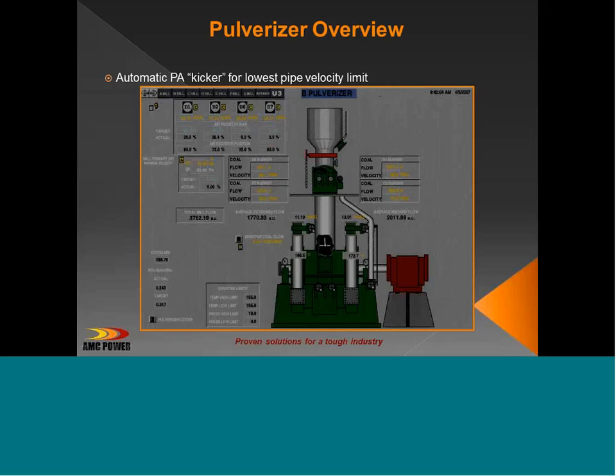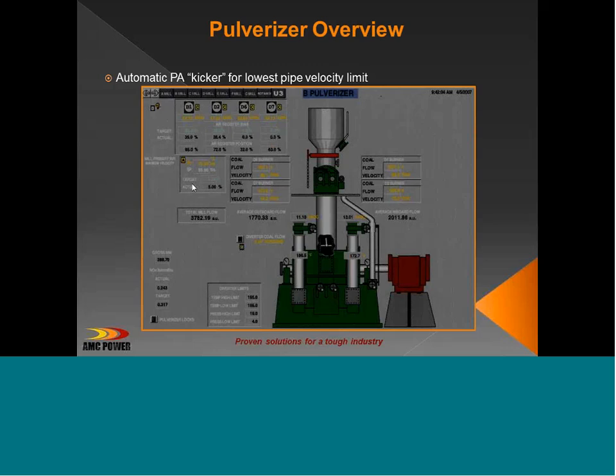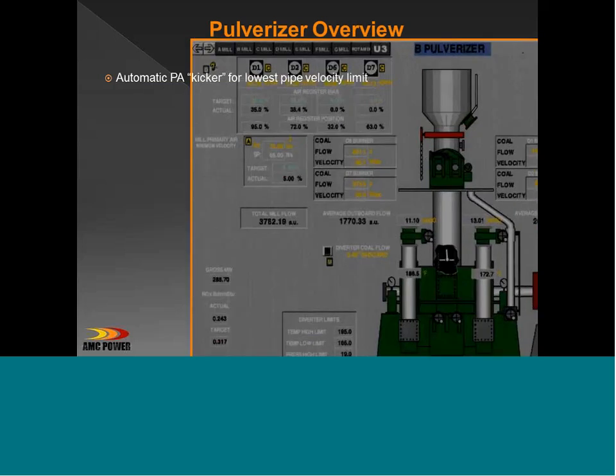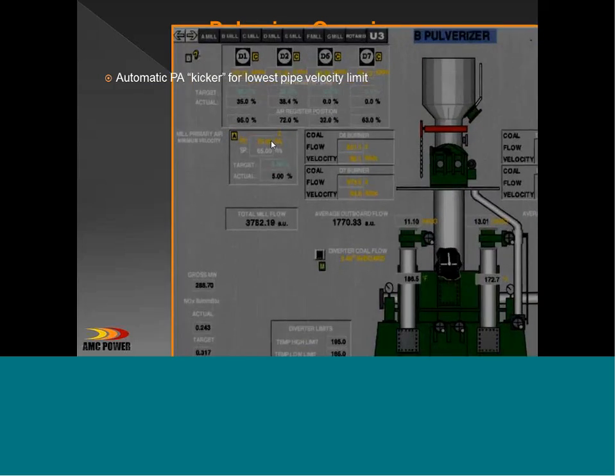But what this screen shows is the comparison of the 4 pipes of a milling system. And in each coal pipe, we're looking at the mass flow and the speed of the coal. And over here on the left is our control block. And in this control block, what we do is we're comparing the coal velocities of each of the 4 pipes. And right now, the process variable is saying our lowest velocity is 75 feet per second. Below that is the set point.